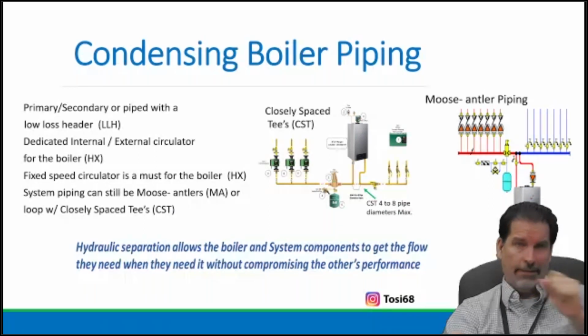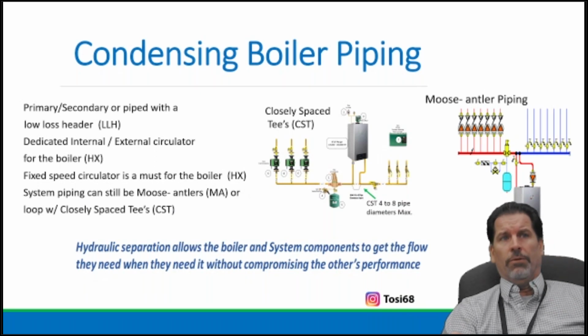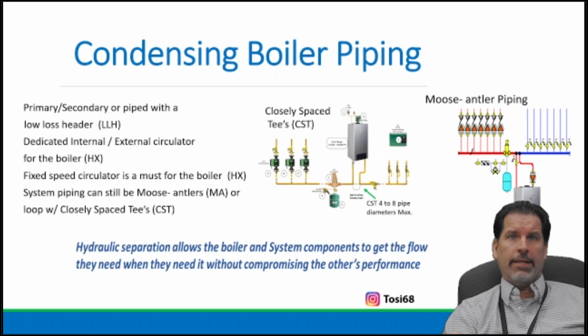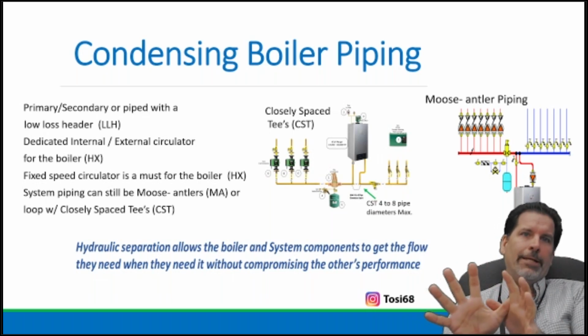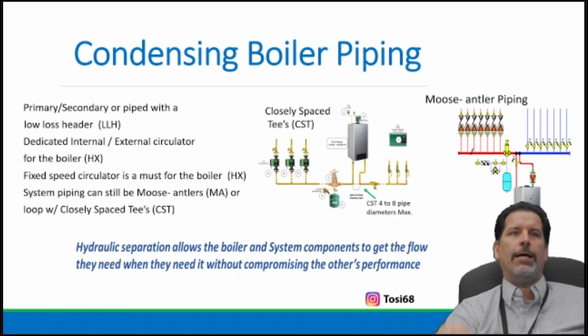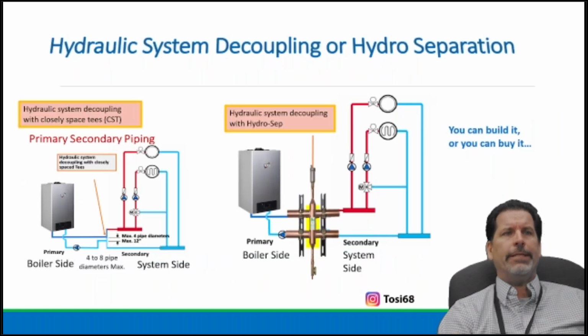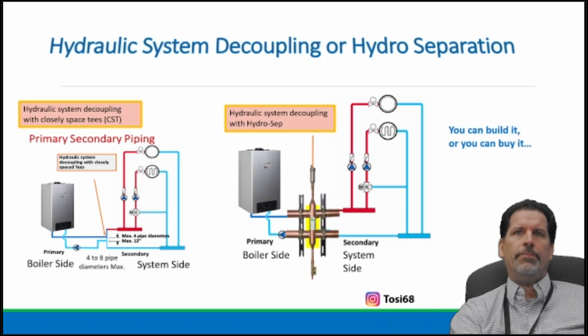We have to understand what hydraulic separation is when working with a condensing boiler. It allows boiler system components to get the flow they need when they need it without compromising other performance. The boiler is separated from the system, and we do that with hydraulic separation. So decoupling or separation can be achieved by building it or buying it.